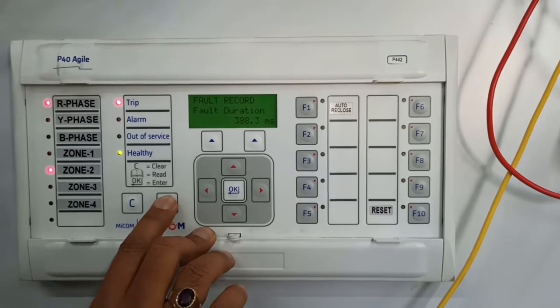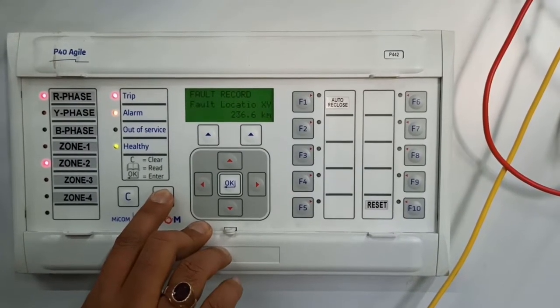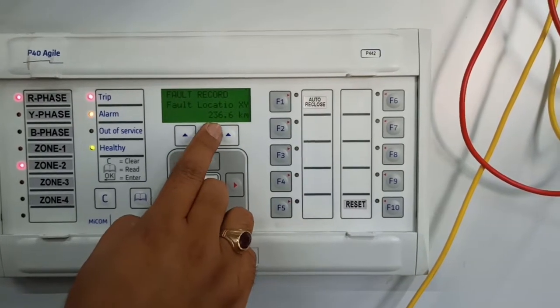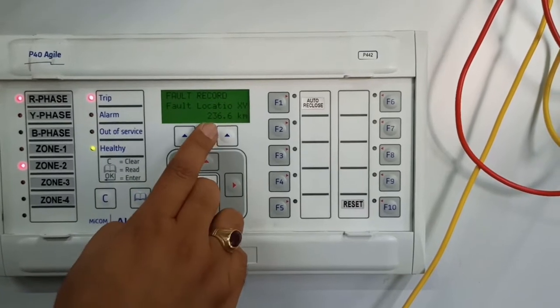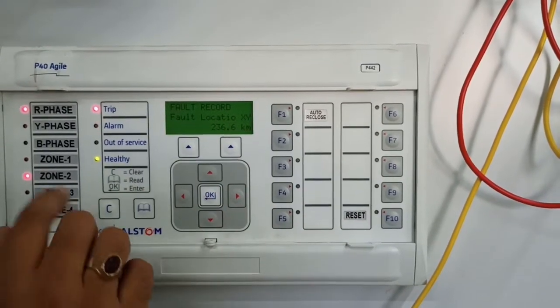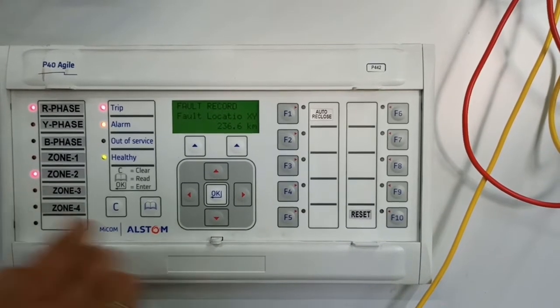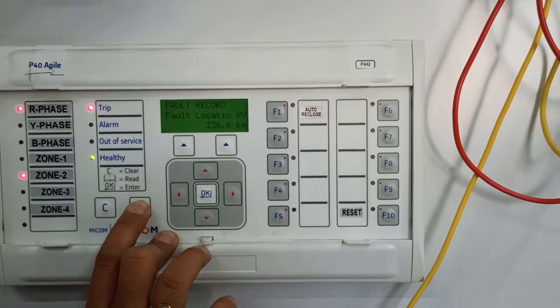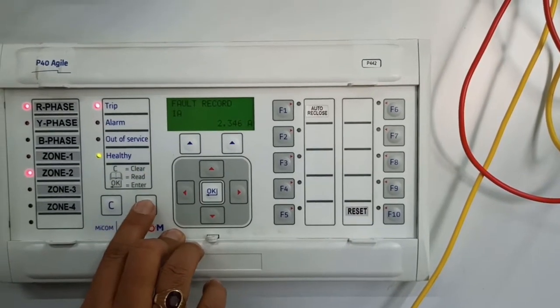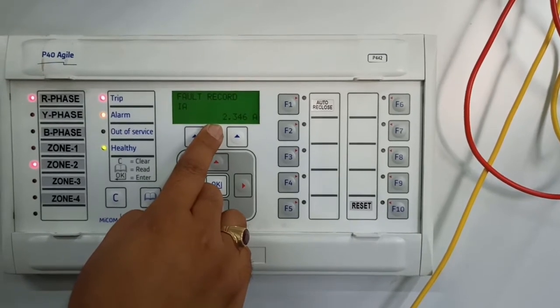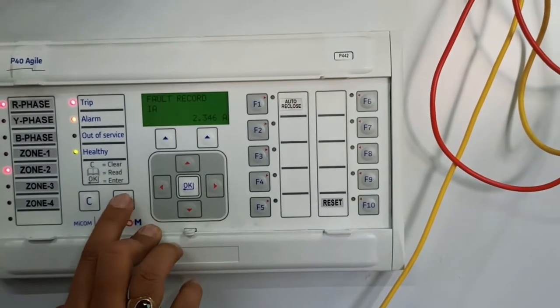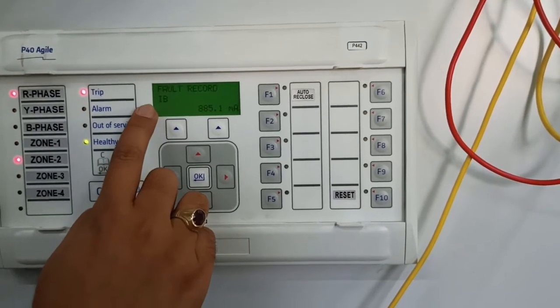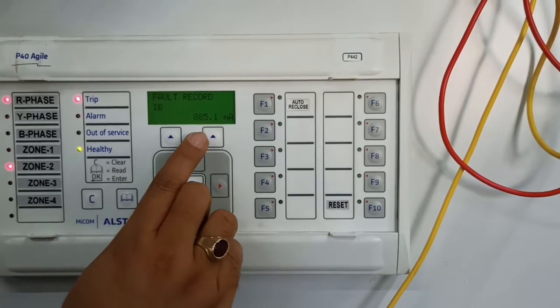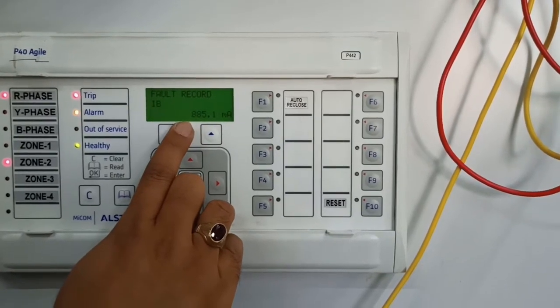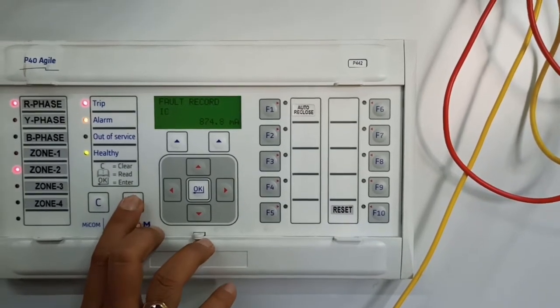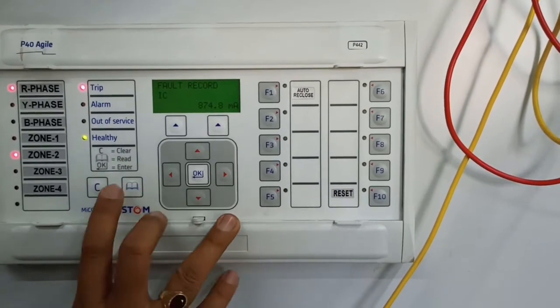Then frequency, fault duration, relay trip time, and fault location is at 236.6 kilometer. When you look at the manual, you will find the values of zone 1, zone 2, zone 3 and zone 4, and from there you can also understand. Then this is IA. The fault is on phase A, that's why its current is high, 2.346 ampere. On B and C there is no fault, so the current is low: 885 milliampere and 874.8 milliampere.